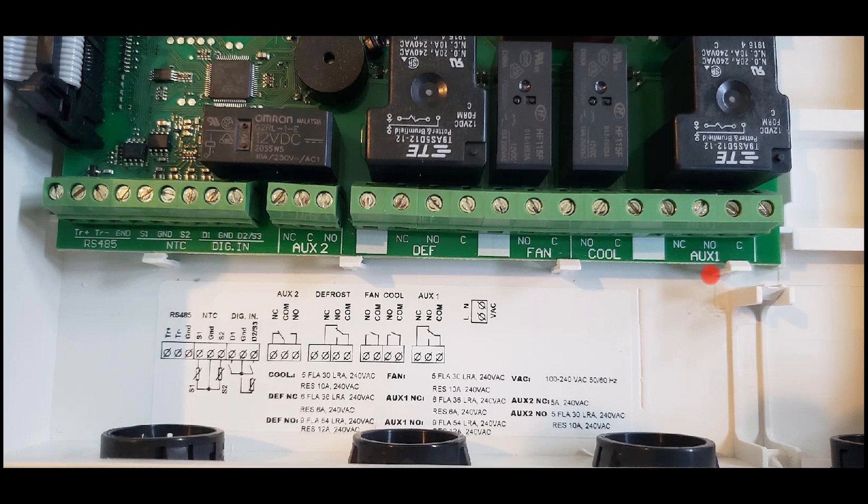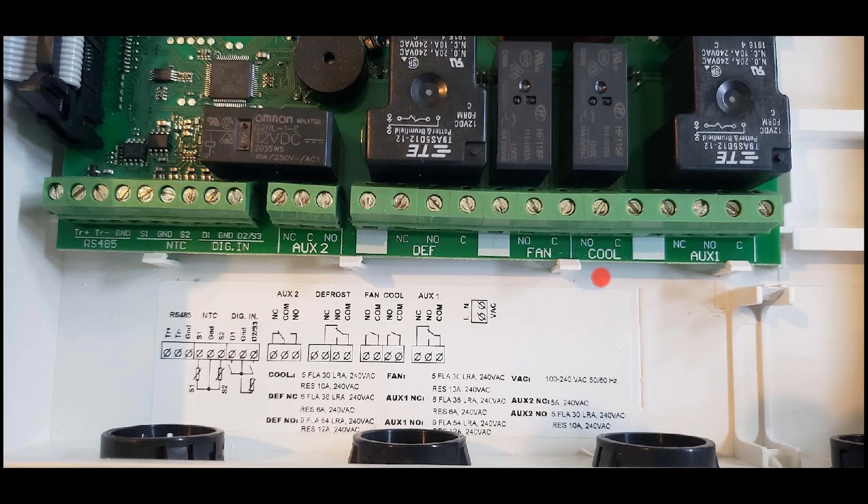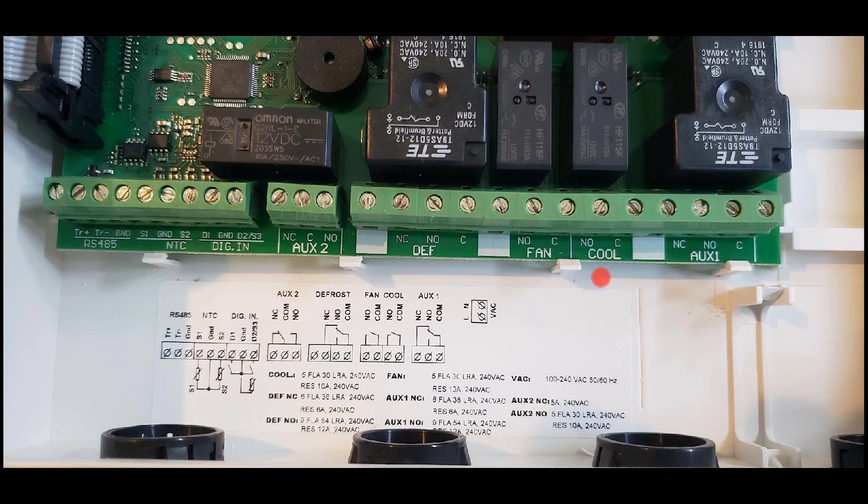Next we have the aptly named cool contact. Most of the time this is used to power the liquid line solenoid valve in refrigeration. When the thermostat calls for cooling, it will energize the liquid line solenoid valve, which opens, provides refrigerant to the metering device, and allows refrigerant feed to the evaporator. When the thermostat is satisfied, it will kill power to that solenoid valve, which will close and stop feeding refrigerant to the evaporator, which is then pumped down by the compressor. The low pressure control then will open up and stop the compressor. And of course, all that reverses once the call for cooling is initiated.